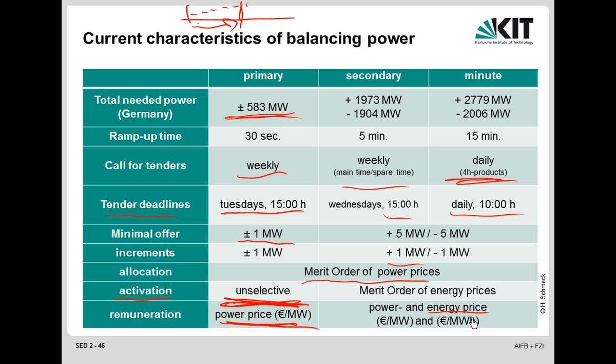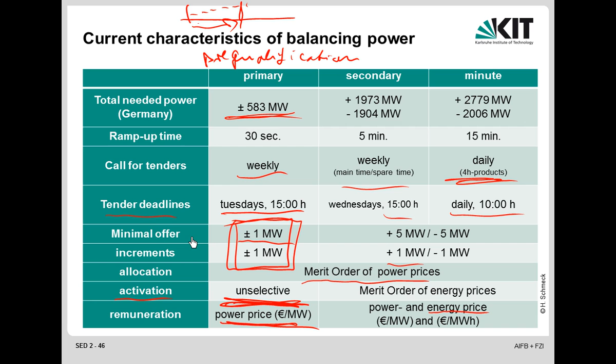Things changed - the minimum size requirements have gone down significantly. You just have to be able to offer a specific amount of power, and you're checked whether you can actually do that reliably. You undergo a pre-qualification exam where the TSOs check whether you're capable of reliably providing, for example, 1 megawatt up and down for the specified minimum period, and that you can provide full power after 30 seconds. If you prove that, you're pre-qualified and can enter the market.